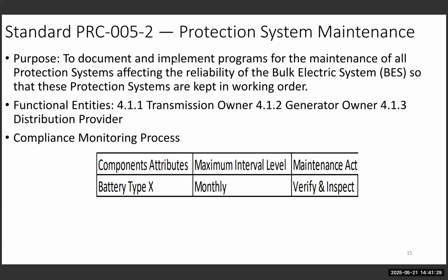So if you read, this is a copy and paste from them. So NERC again is the North American Electric Reliability Corporation. They come up with all the rules to ensure reliability for the grid. So, you cannot have a reliable grid if the relays are not operated well. You cannot have a reliable grid if the battery rooms are not charged to act when there's a failure. So here, to document and implement programs for the maintenance of all protection systems affecting the reliability of the bulk electric system so that these protection systems are kept in working order.